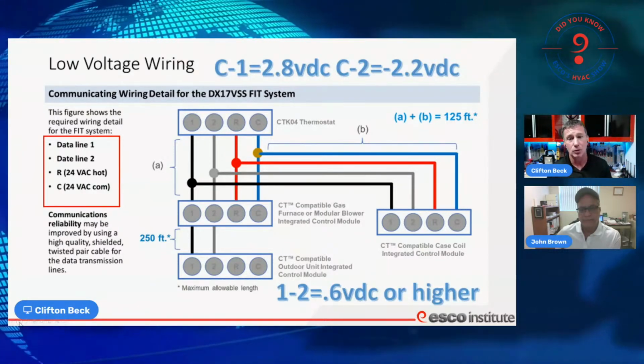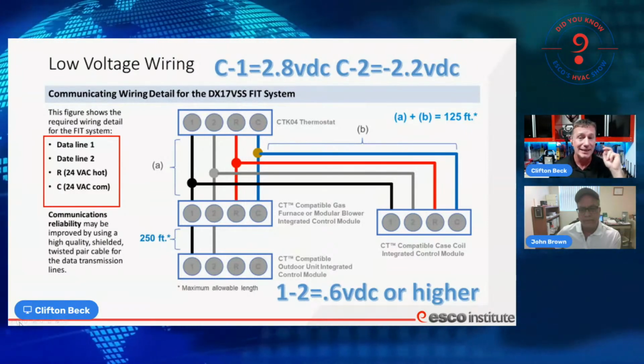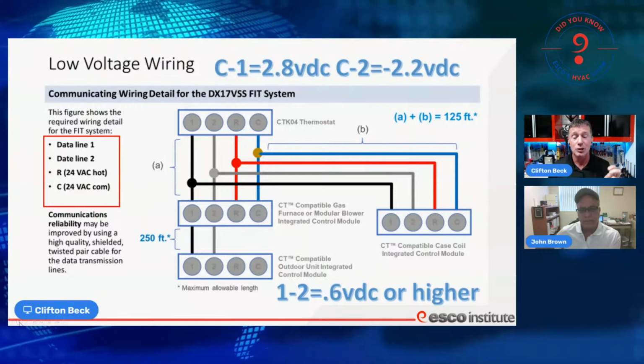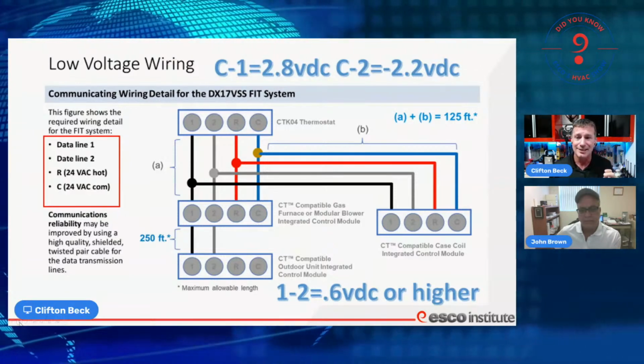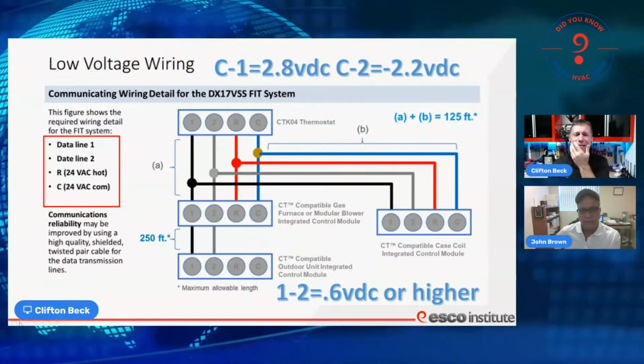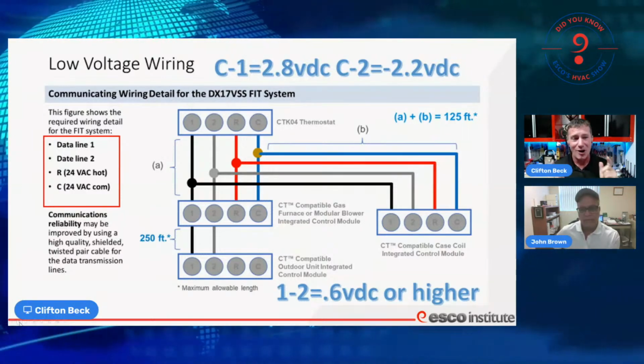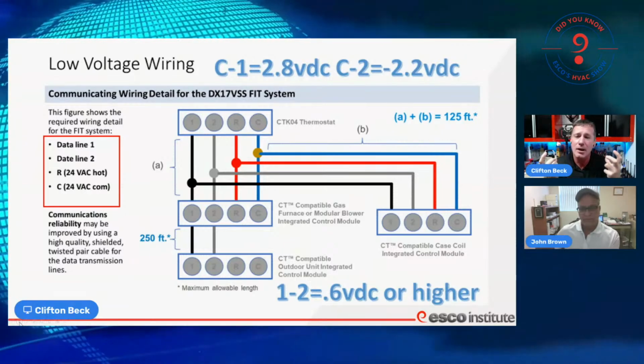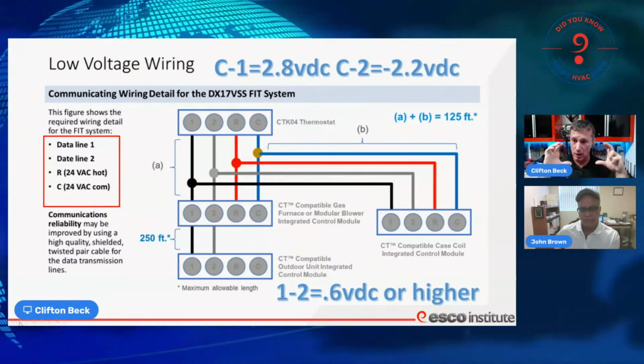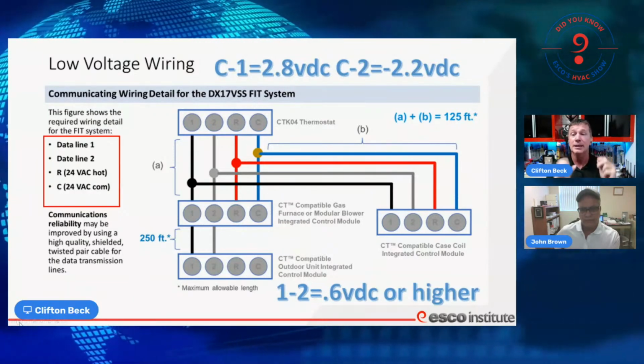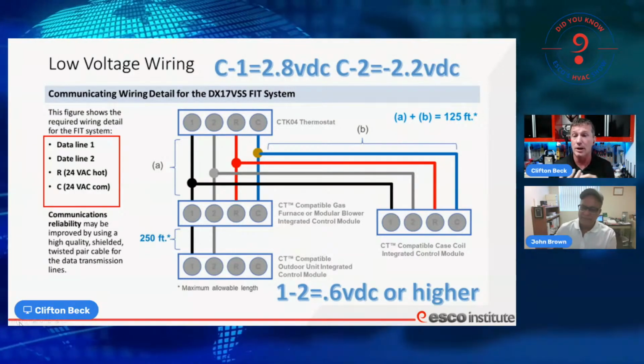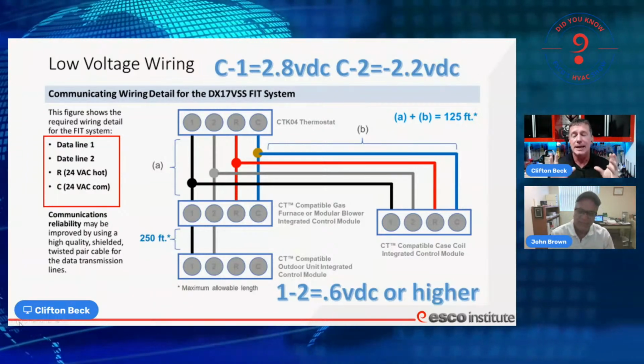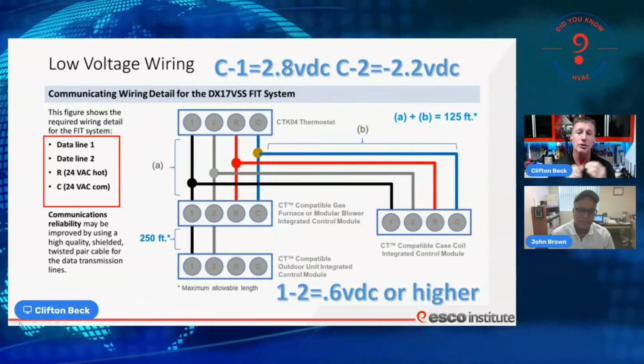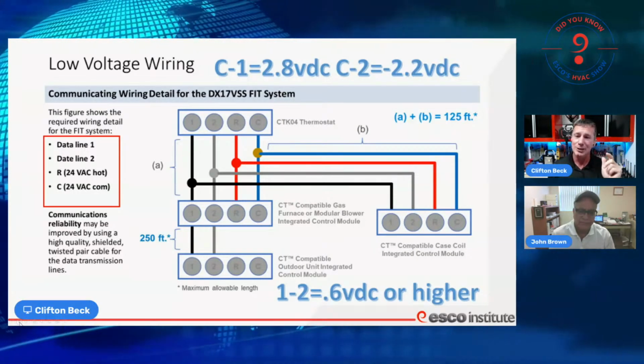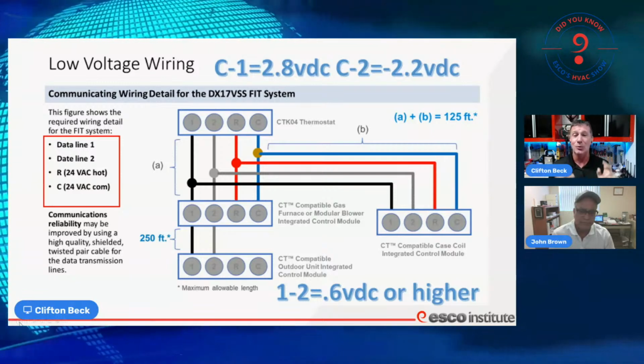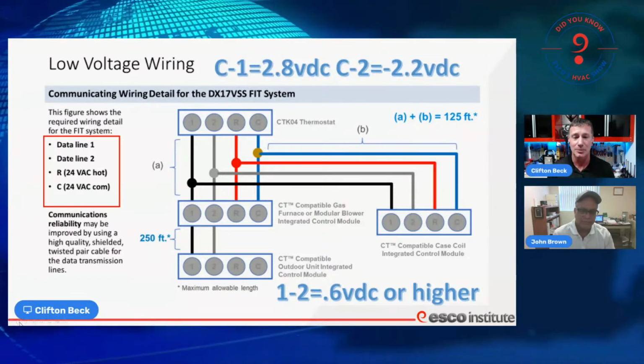Where I put that little red square on our diagram, we have data line 1, data line 2, and then two additional wires for 24 volts hot. Why do we do that? Our 24 volts hot, R and C, provides the higher amount of current, the power we use to run that big fancy colored LED screen. It also gives us the capability of running Bluetooth and Wi-Fi and any other load that's on our controller. Data 1 and data 2 are our 5 volt DC signals that we use to communicate — that's our parallel communicating network.